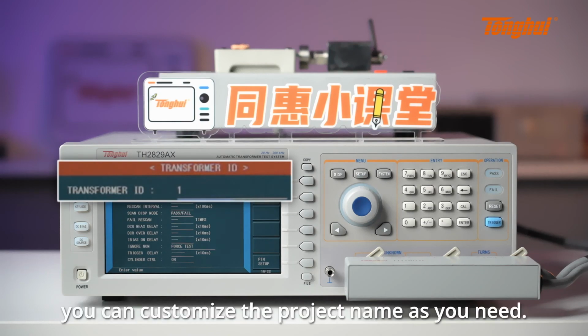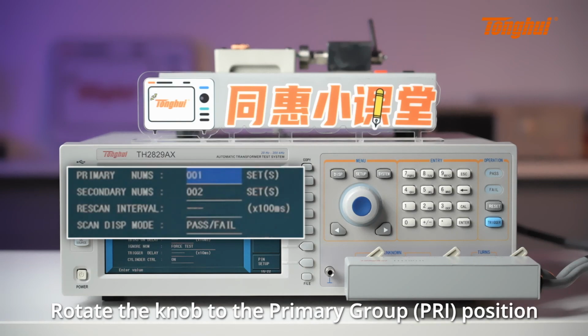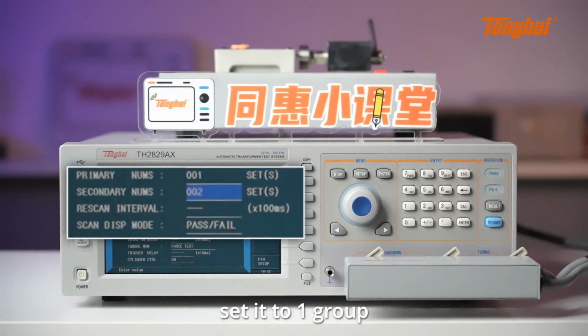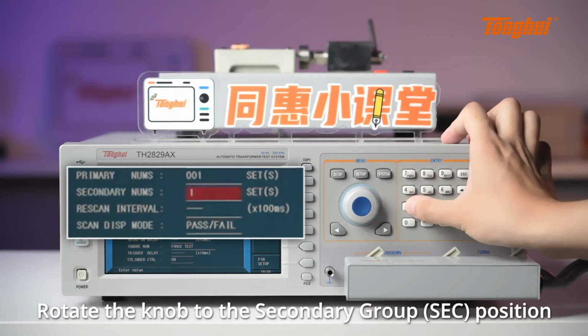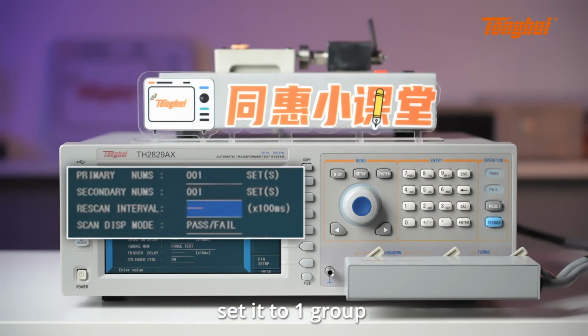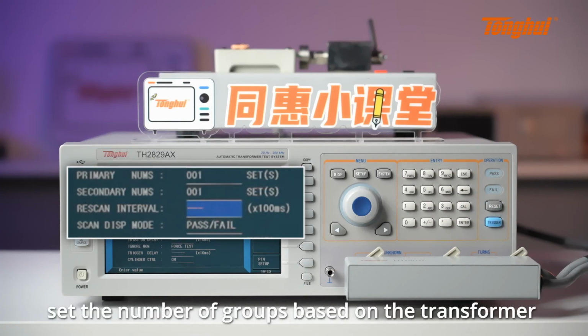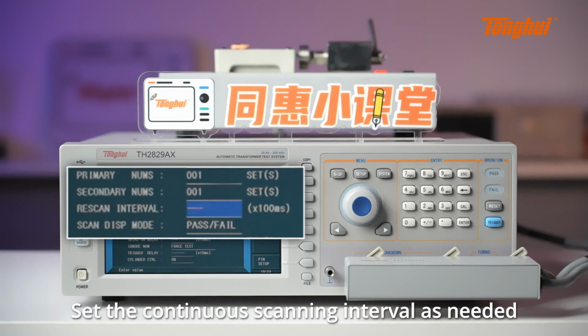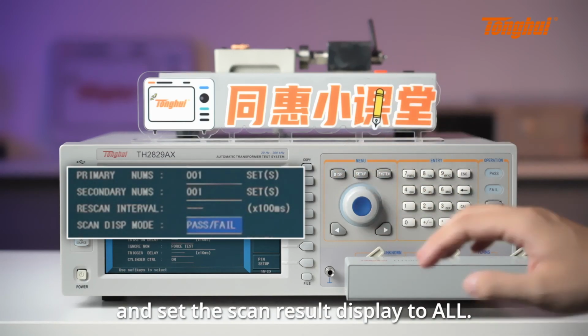You can also customize the project name as you need. Rotate the knob to the primary group position. Set it to 1 group. Rotate the knob to the secondary group position. Set it to 1 group. Set the number of groups based on the transformer you are using. Set the continuous scanning interval as needed and set the scan result display to all.